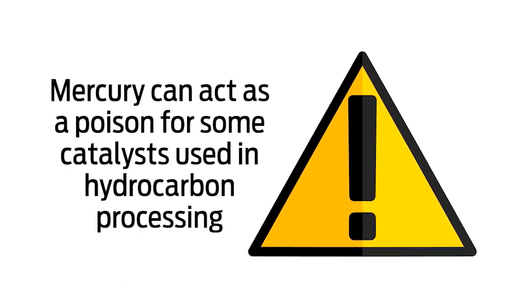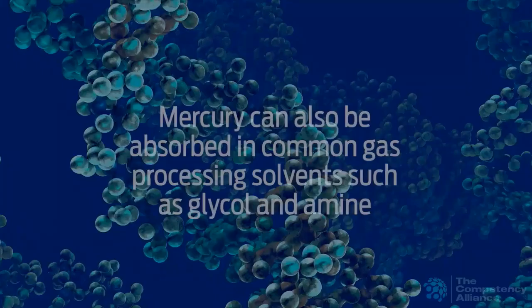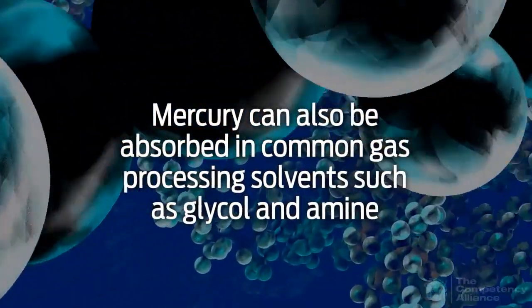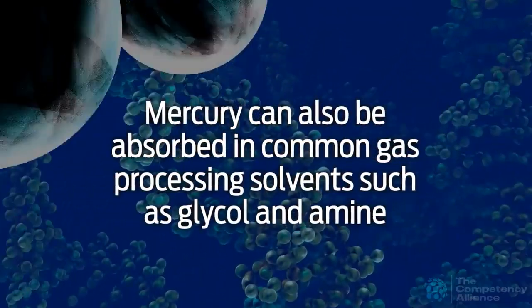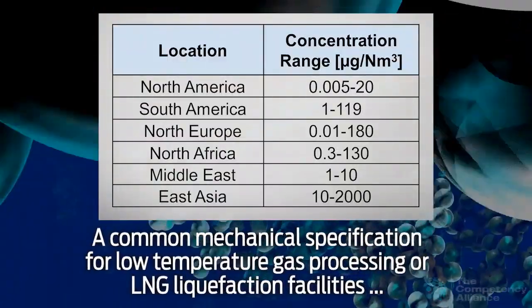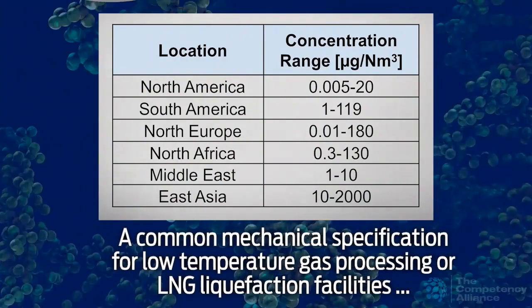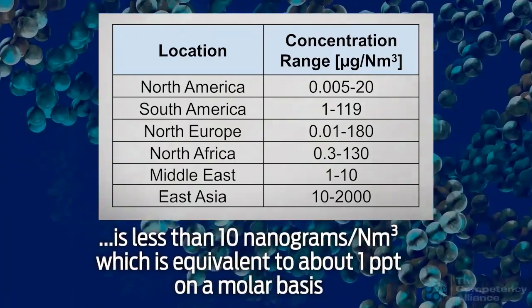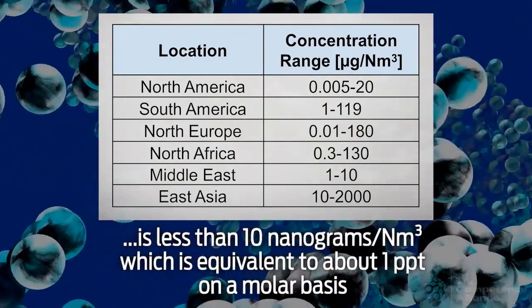Mercury can also act as a poison for some catalysts used in hydrocarbon processing. Mercury can also be absorbed in common gas processing solvents, such as glycol and amine, and will concentrate in the vapor stream leaving the regeneration system. A common mechanical specification for low-temperature gas processing or LNG liquefaction facilities is less than 10 nanograms per normal cubic meter, which is equivalent to about 1 ppt on a molar basis.